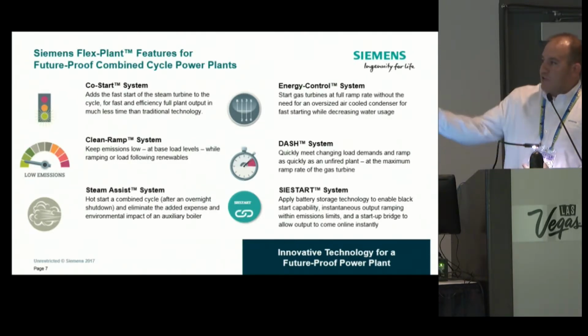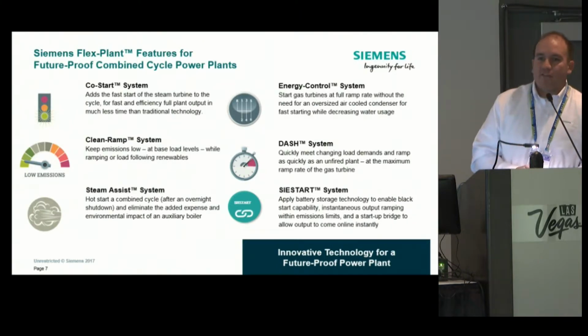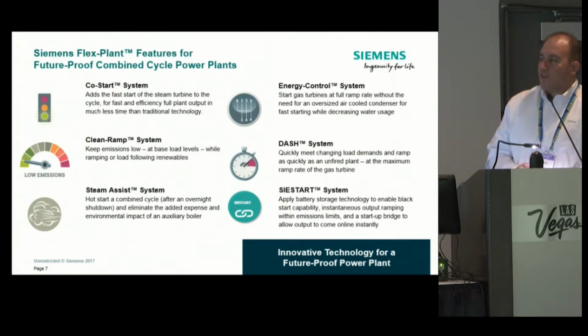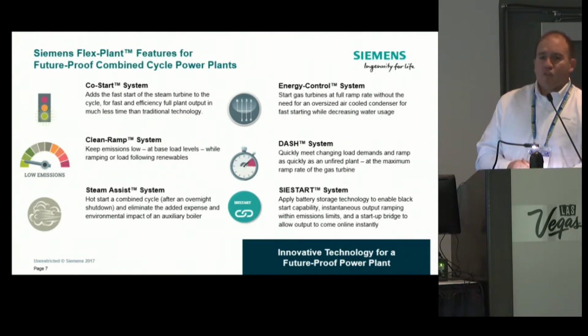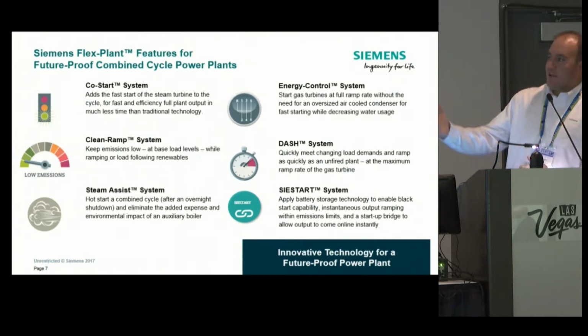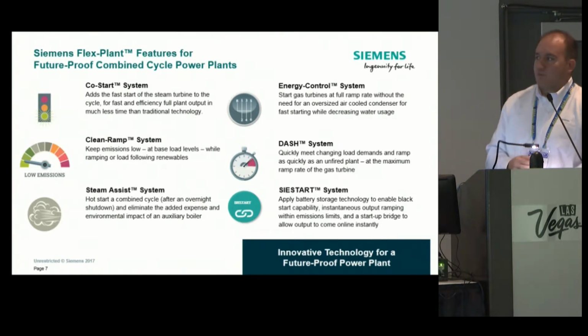But energy control, steam assist, again, concepts to reduce cost or drive down the cost of that power plant. One of them is to reduce cycles of an ACC, and the other is to reduce the use of your aux boiler. Dash system and clean ramp, those both get you into that ramping stage. The dash system lets you ramp your fired combined cycle plants at a gas turbine ramp rate. The clean ramp system keeps you in emissions while you're doing this ramping up and down. So those are the different technologies attacking there.